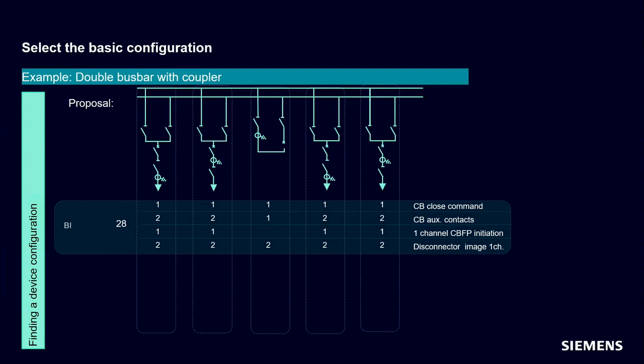We need 1 binary input for each feeder to activate the circuit breaker failure protection in the feeder. Typically, you have no externally started circuit breaker failure protection in the coupler, so we don't need it. And for the disconnector image, we have 2 busbar disconnectors in each feeder. And as we said, just to say that it's possible, we are using only one binary input in this example. So we need 2 binary inputs per feeder for the busbar disconnectors.